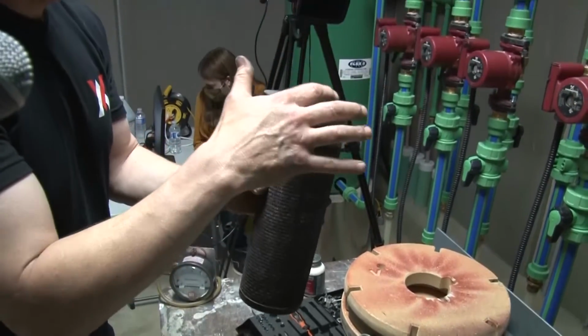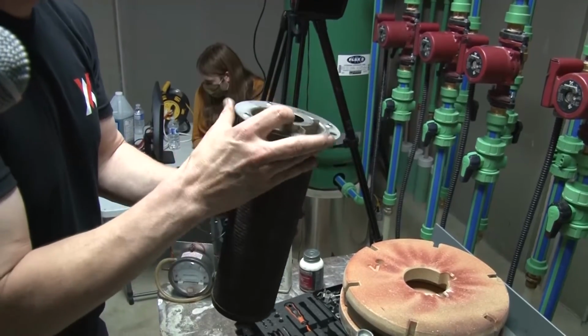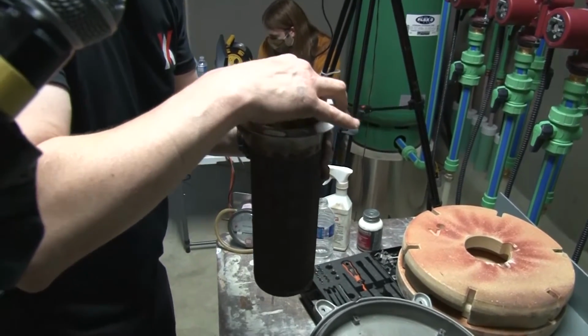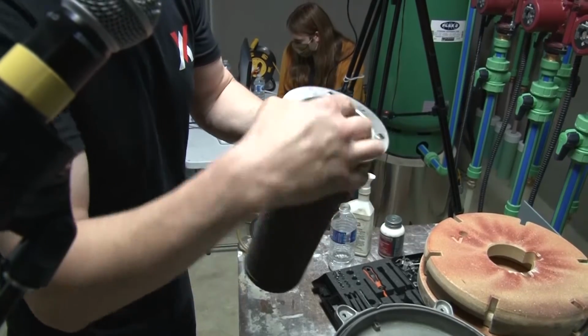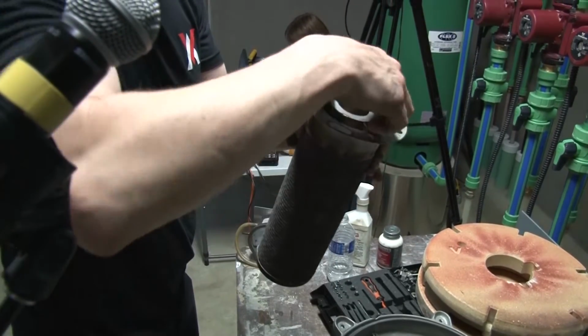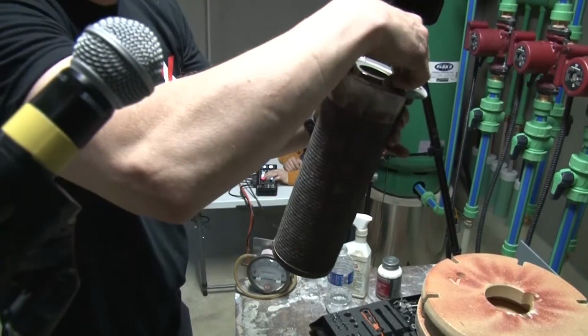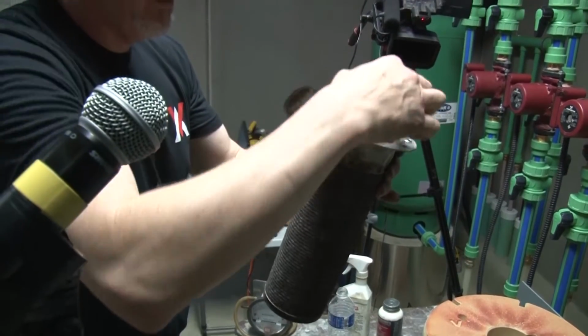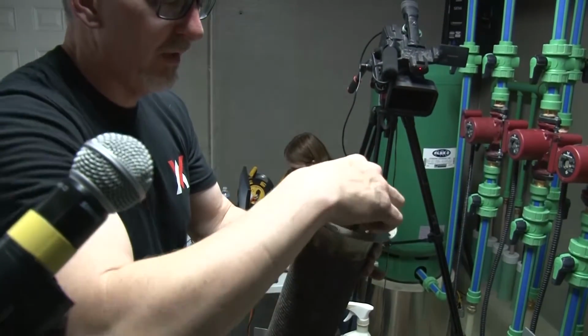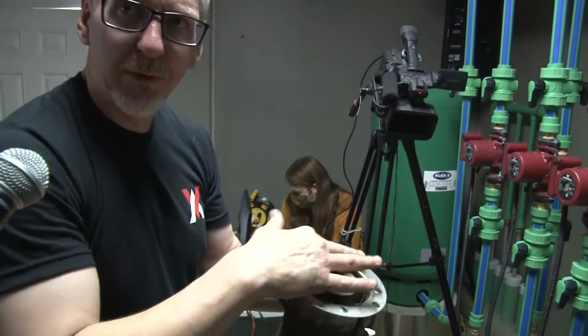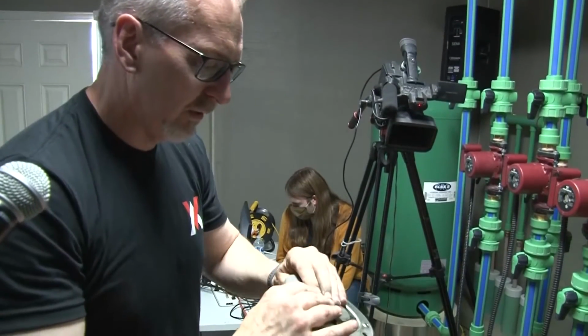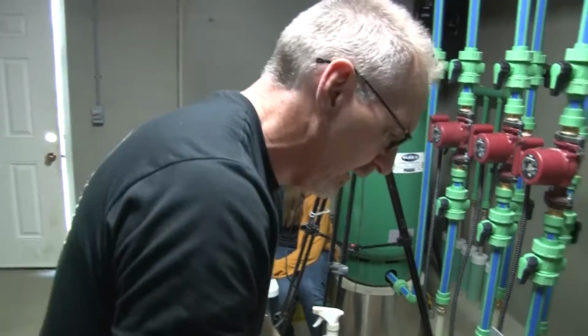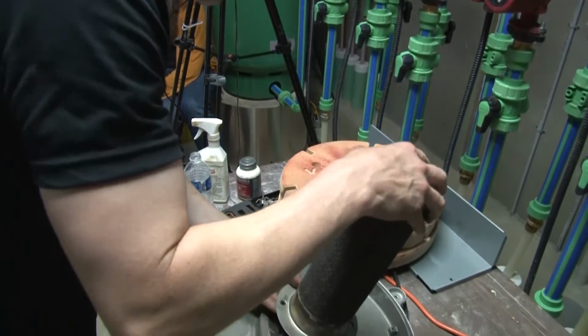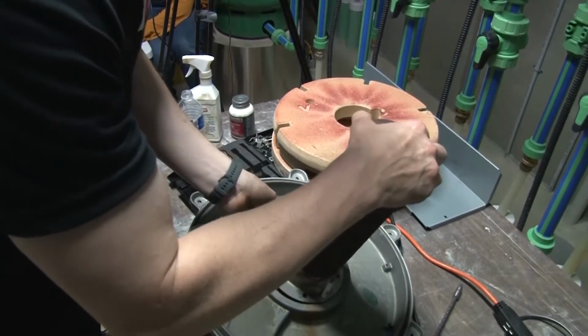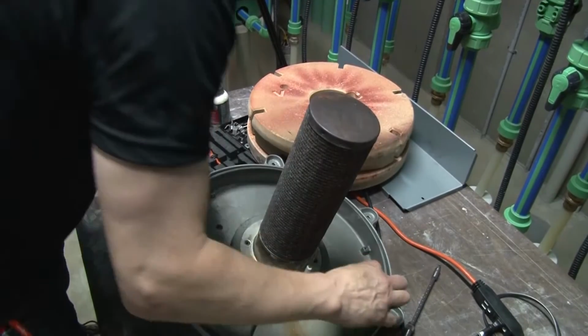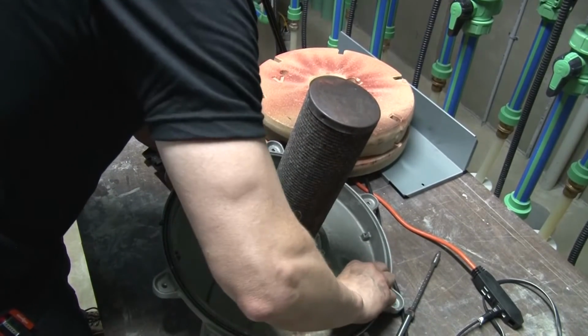Right, I don't want to do that. See how basically the turbulator is actually still standing up. There's a slot that it needs to sit into. See how that's now nice and flat in there? If this is not installed correctly, you've really got to be careful that seat's in there. Otherwise, you put this down and you put the bolts in. You think you got that sealed, but now you've got an opening there, so it's not going to close off properly for us. So we'll slide that back in. It's like deja vu. There we go. That's all the French I know.